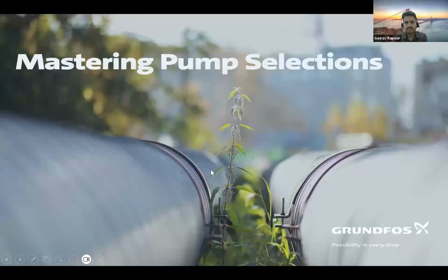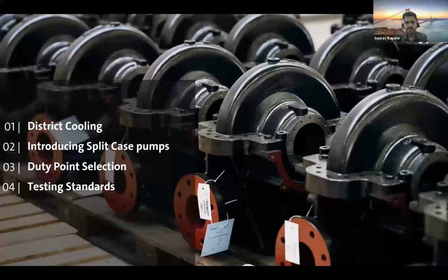So today's topic for our knowledge sharing session is mastering pump selections. As I conveyed, I belong to Grundfos. I work in Grundfos Pumps, where we manufacture centrifugal pumps. The agenda for today is we'll quickly look into district cooling, because sir has already covered the majority of it. Then we will jump into introducing split case pumps, which are the main heartbeat of any DCS. These are the large, mammoth-size pumps which are used to circulate a large amount of flow. For example, 500 liters per second, 700 liters per second at 35 meter head, 45 meter, 50 meter head. These are the machines which help in production of water through chillers, deliver it to the end users, and also in the cooling towers. Then we'll quickly look into duty point selection.